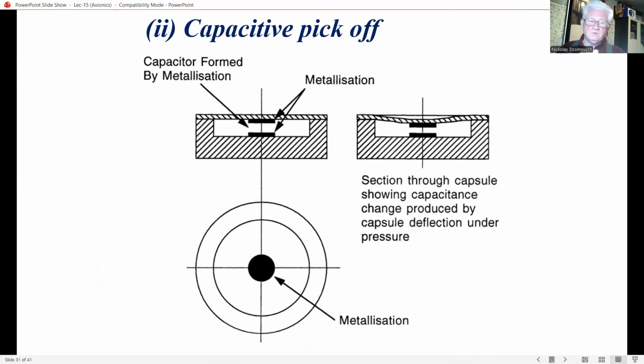But it should be noted that the solid-state capsule types of pressure sensor have an inherent sensitivity to acceleration because of the mass of the diaphragm. The sensitivity is small and can generally be ignored if the pressure sensors are mounted so that their sensitive axes are orthogonal to the normal acceleration vector.